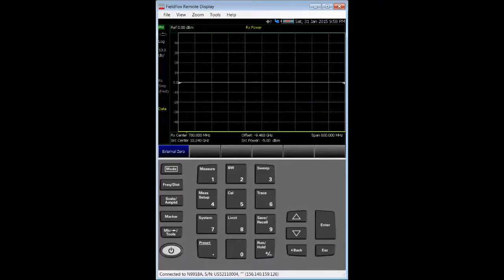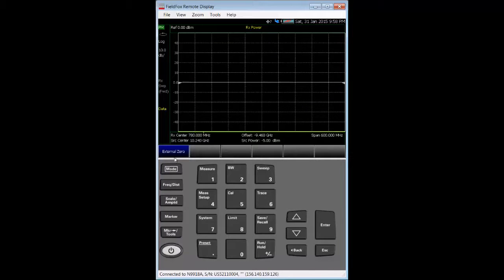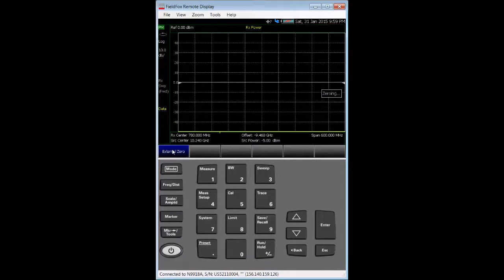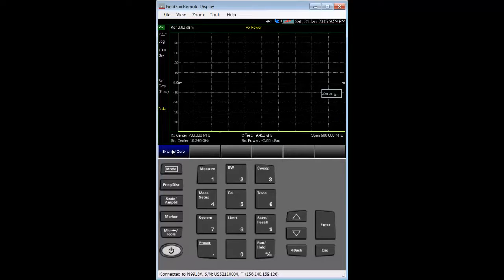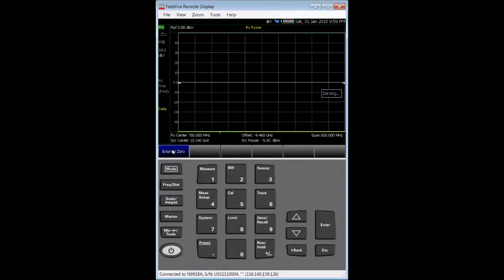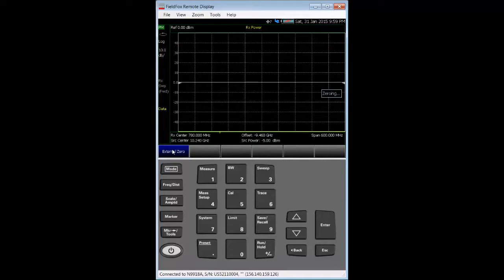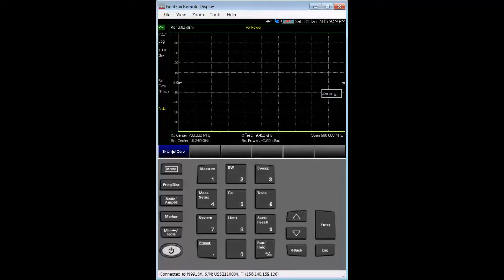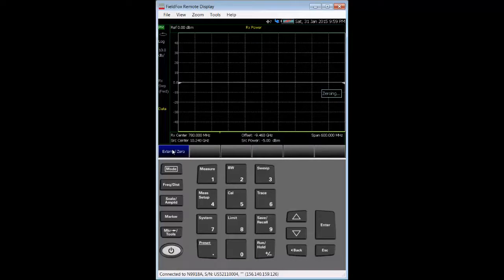I press the external zero soft key. Upon doing so, we see a zeroing message on the right side of the display while the USB power sensor is zeroed. And it's important to note that no power flows into the sensor during this part of the procedure. So, the power sensor should have nothing connected to the RF input connector while zeroing. An amber light on the USB power sensor is lit during the zeroing. This process takes about 20 seconds or so. The zeroing indicator goes away when the process is complete.